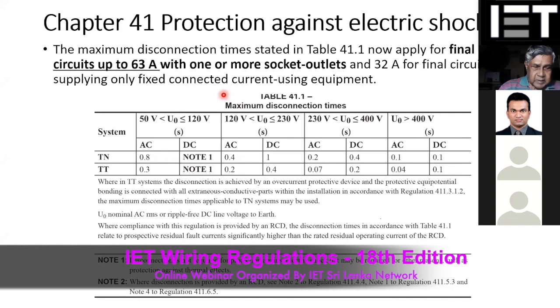For circuits less than 32 ampere, this table should be followed, where depending on the voltage level, for example, less than 230 volts AC, which we are using, if it is a TN system, then the earth fault protection should operate in less than 0.4 second or 400 millisecond. If it is a TT, it's 0.2 second or 200 millisecond. Now this is extended up to 63 ampere. So if it is a final circuit with one or more socket outlets up to 63 ampere, this rule should apply. Earlier it was only up to 32 ampere.